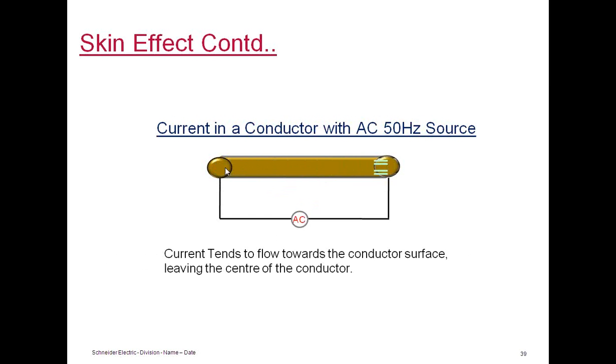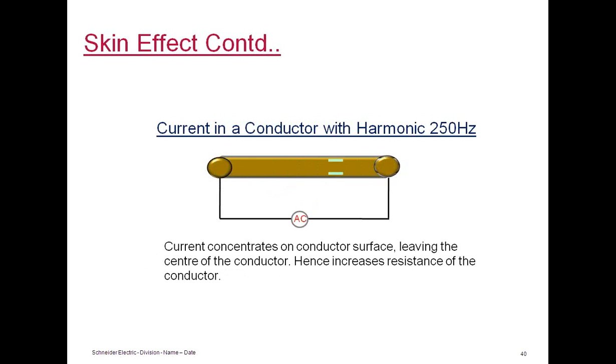Therefore, the resistance of the conductor will increase with high frequency because of the tendency of the current to flow towards the conductor surface. If we apply, let's say, fifth harmonic current, 250 Hz current, this is how it looks. The speed is 5 times, and the center part of the conductor is not used at all to flow harmonic current. So harmonic current will flow towards the surface of the conductor. That means you're going to have less area to flow high frequency harmonics. As per theory, we can assume resistance of a conductor will increase linearly with frequency. That means if we have a resistance of 1 ohm at 50 Hz, we can assume it will be 5 ohms at fifth harmonic frequency, and 7 ohms at 7th harmonic frequency, and so on and so forth.